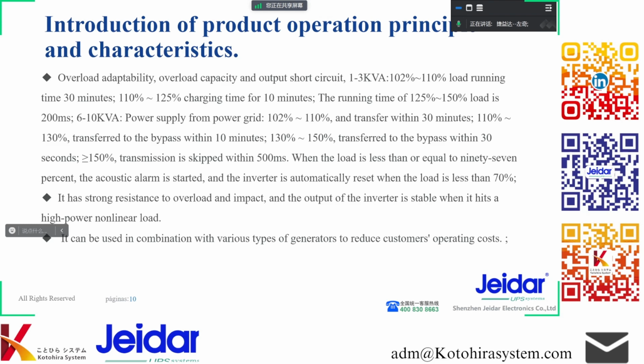When the load is less than or equal to 97%, the acoustic alarm is started and the inverter is automatically reset when the load is less than 70%. It has strong resistance to overload and impact, and the output of the inverter is stable when it hits a high power nonlinear load. It can be used in combination with various types of generators to reduce customers' operating costs.